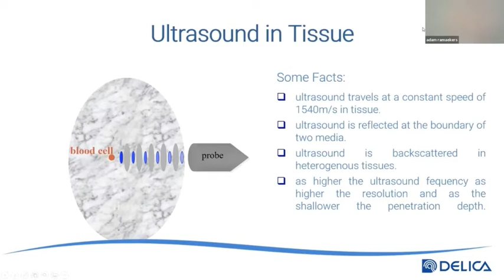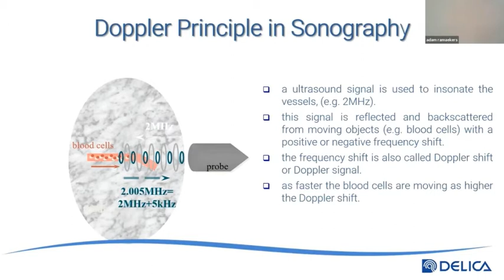Here you see it in sonography: ultrasound signals are used to insonate the vessels at 2 MHz. The signal is reflected and backscattered from moving objects, the blood cells, with a positive or negative frequency shift, as we all know. The frequency shift is also called the Doppler shift or Doppler signal. The faster the blood cells are moving, the higher the Doppler shift. And here you see that an angle error of up to 45 degrees will be accepted.